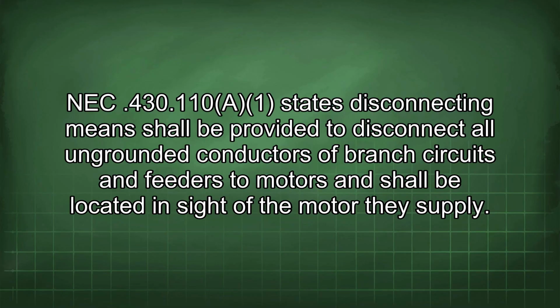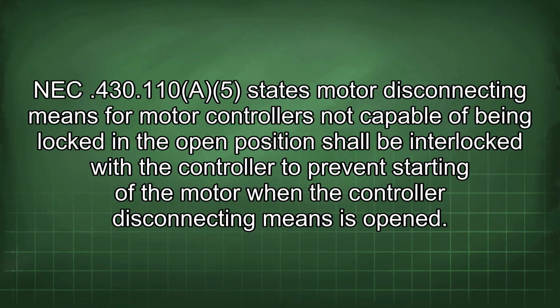NEC 430.110 states disconnecting means shall be provided to disconnect all ungrounded conductors of branch circuits and feeders to motors and shall be located in sight of the motor they supply. NEC 430.110 states motor disconnecting means for motor controllers not capable of being locked in the open position shall be interlocked with the controller to prevent starting of the motor when the controller disconnecting means is opened.